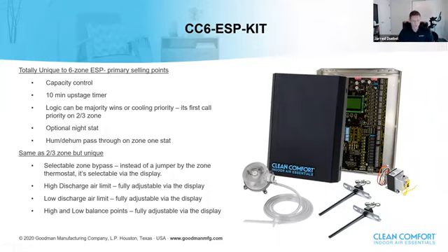We have humidification and dehumidification pass-through on the zone 1 stat, which means if you have a humidifier or dehumidifier, you can land those wires right on our zone control panel from the stat and then out to the equipment. It's just a pass-through. It doesn't change the humidifier or dehumidifier. It just sends on the signal from the thermostat. It makes it easier for the contractor to be able to consolidate all that wiring in one place.